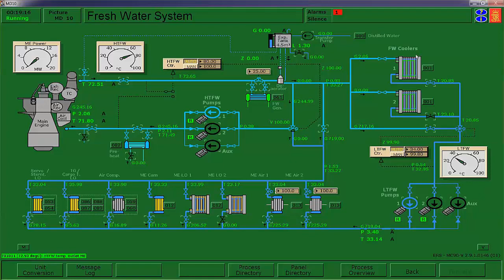So this is all automatic. I don't really have to worry about it. It sees that this could be depressing the main engine, and it will automatically recirculate the water back. So let's go back and look. What we're seeing, and you notice now actually the temperature is starting to come back up again. But anyway, this is in free recirculation, full recirculation, no flow back for cooling. And that recirculation valve is almost wide open here too. So most of the water is recirculating, and I don't have to worry about the main engine being subcooled or being cooled too severely. It's all automatic.